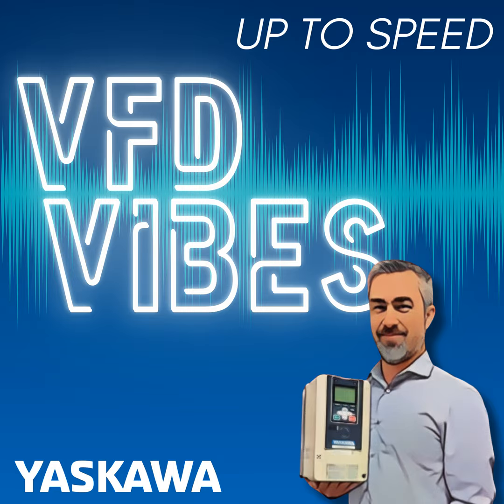System grounding is the intentional connection of a phase or a neutral conductor to ground for the purpose of controlling the voltage with respect to earth or ground within predictable limits, and providing for a flow of current that will allow detection of unwanted connection between system conductors and ground. Now, that's right out of IEEE Standard 142. Such detection may then initiate operation of automatic devices to remove the source of the voltage from these conductors.